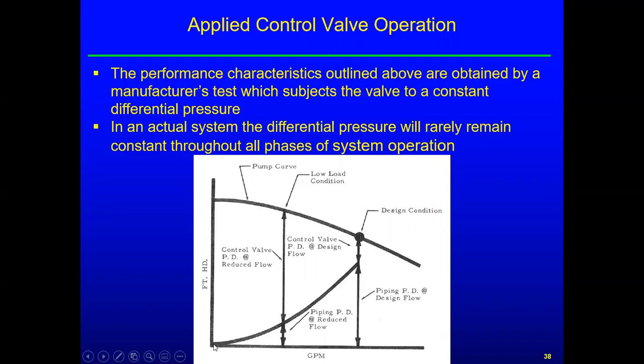And going through the origin down here at 0, 0 indicates there's no static head or no static lift in the system as we might have, say, with a cooling tower. Okay. Well, so if you were throttling this system, say we don't need design flow, maybe we need 50% of design flow, you get back to this intermediate point, and we see at the lower flow rate, the pressure drop of the piping has diminished significantly. Okay, so it's actually a factor of 4, because the pressure drop falls as the square of the velocity. And if the flow is 50%, the velocity is 50%. So down to the system curve at the reduced GPM, the feet of head on the vertical axis would basically be 1/4 of that at the design flow.